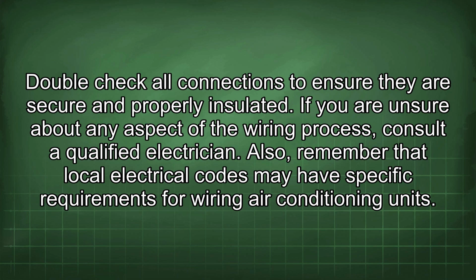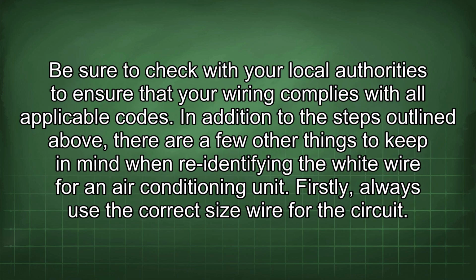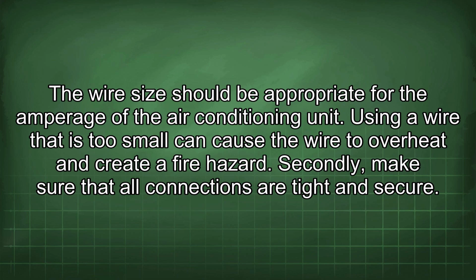Also, remember that local electrical codes may have specific requirements for wiring air conditioning units. Be sure to check with your local authorities to ensure that your wiring complies with all applicable codes. In addition to the steps outlined above, there are a few other things to keep in mind when re-identifying the white wire for an air conditioning unit. Firstly, always use the correct size wire for the circuit. The wire size should be appropriate for the amperage of the air conditioning unit. Using a wire that is too small can cause the wire to overheat and create a fire hazard.